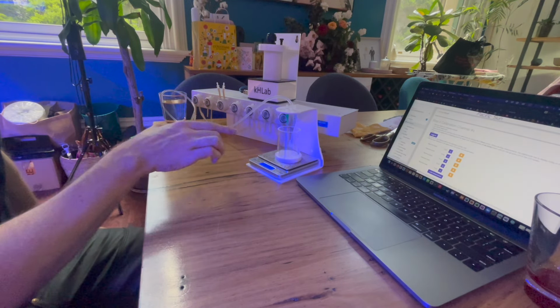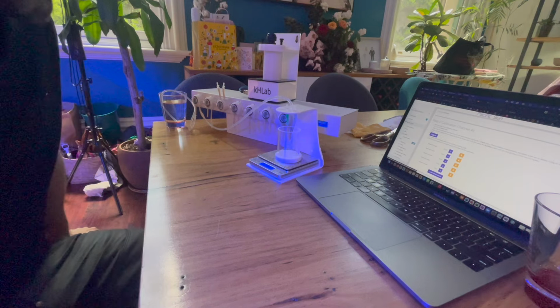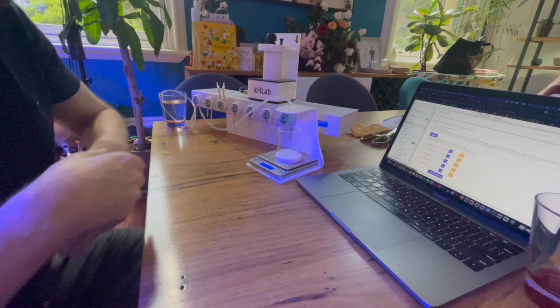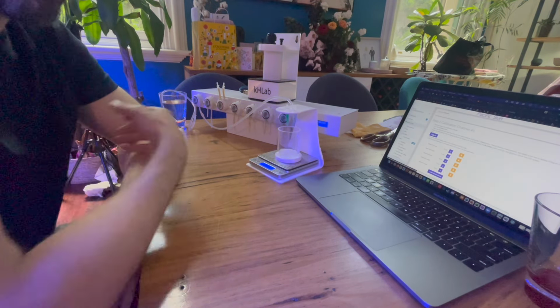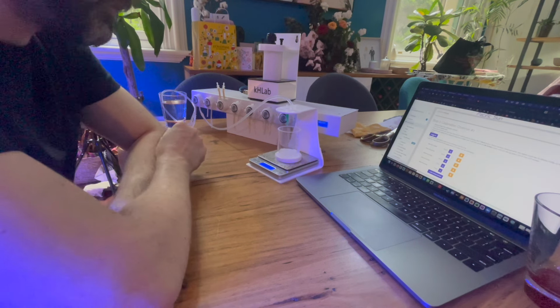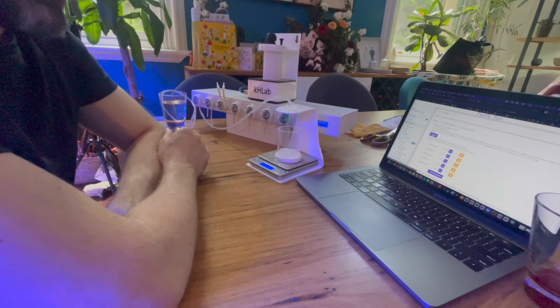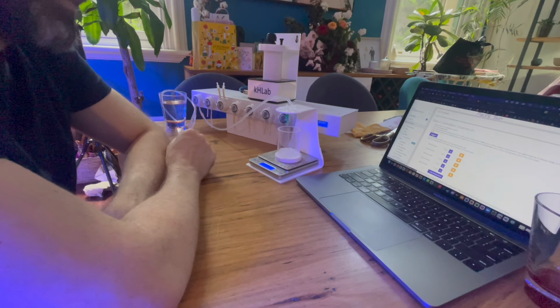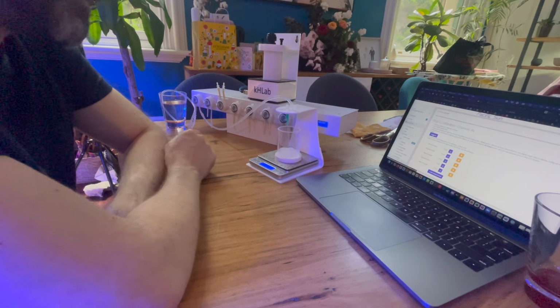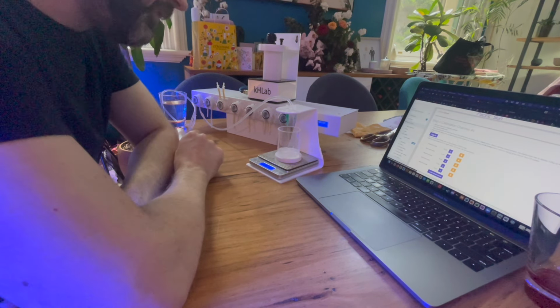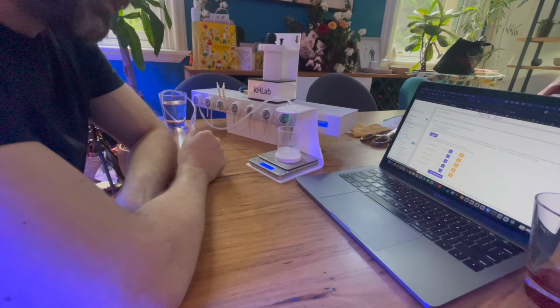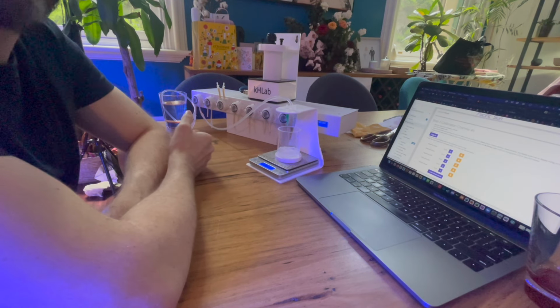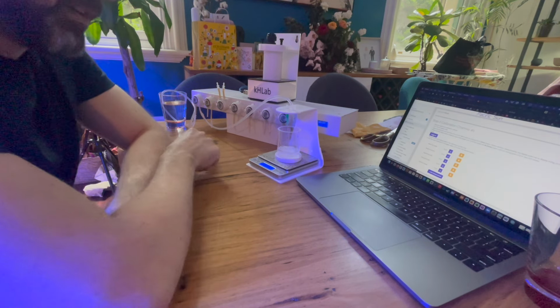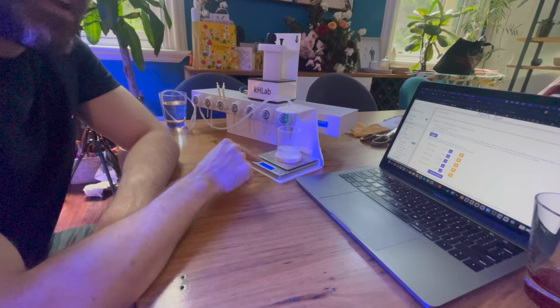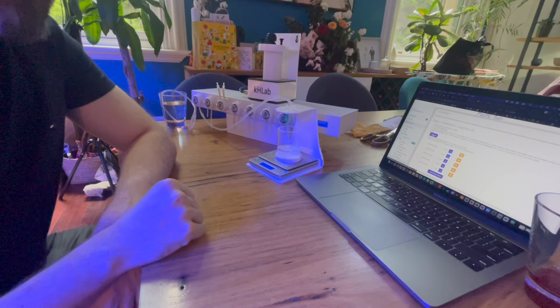And as you can see, it's now pumping water into the vial, and we just have to wait for it to stop automatically. It'll just take a few seconds. It's going to pump approximately 70 grams of water. Now, it might be a little bit more, it might be a little bit less. It doesn't really matter, because what the final value ends up being will be recorded on the scale, and that's what we enter here on the interface in the website.